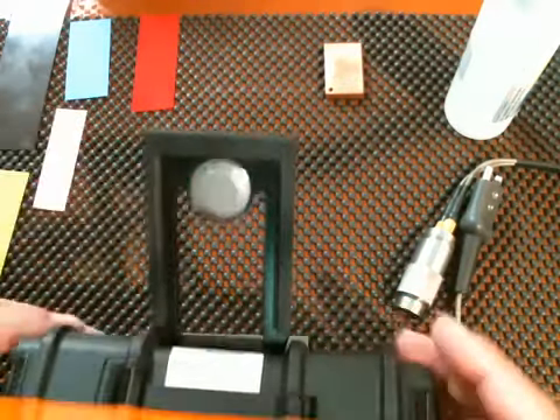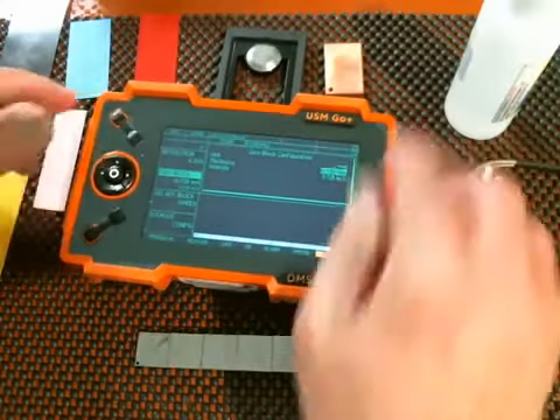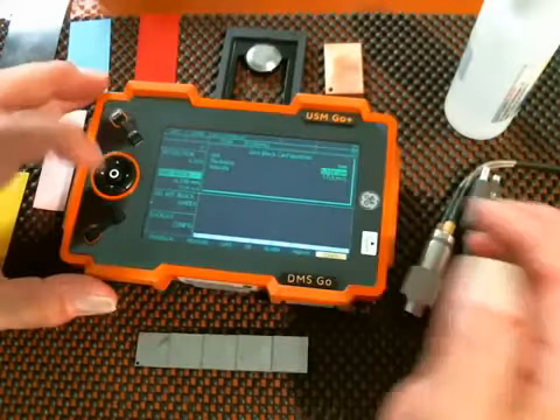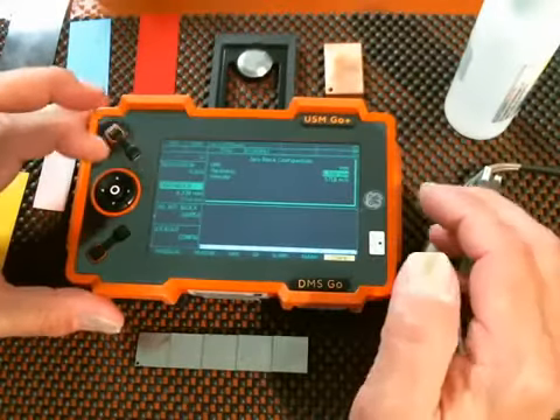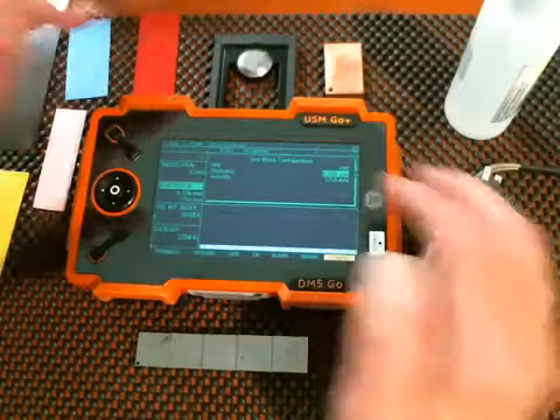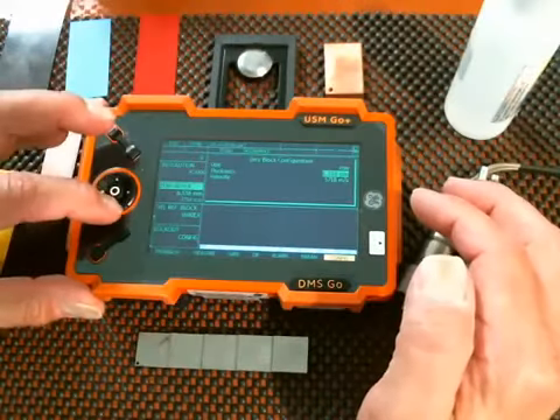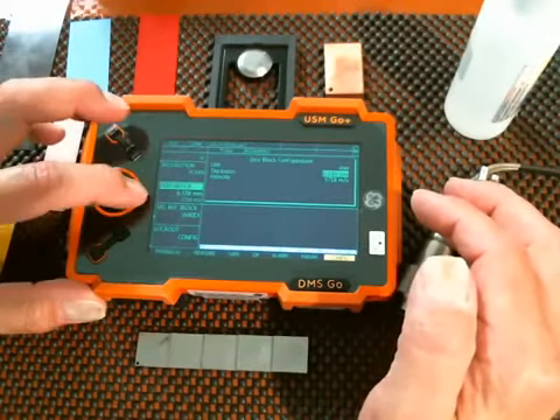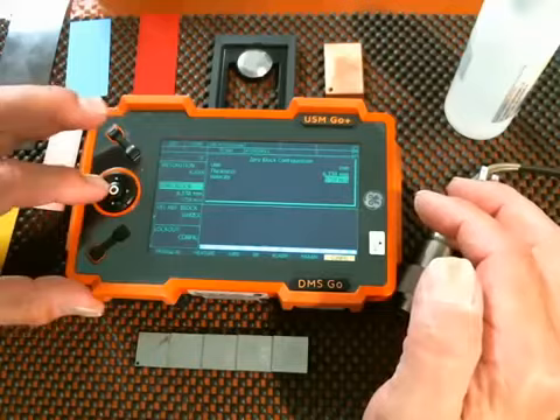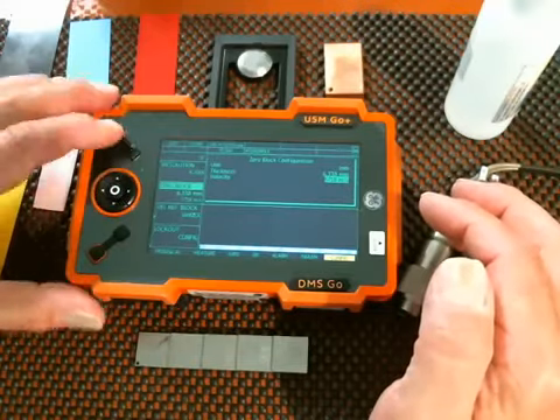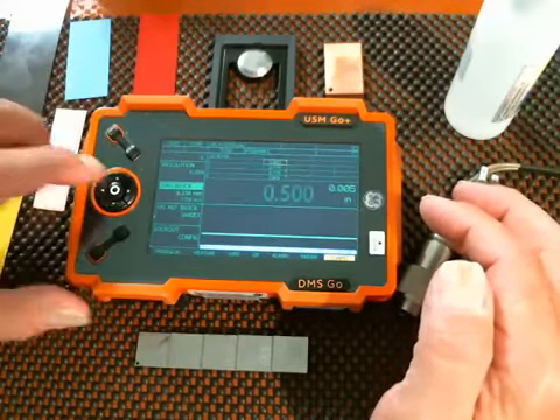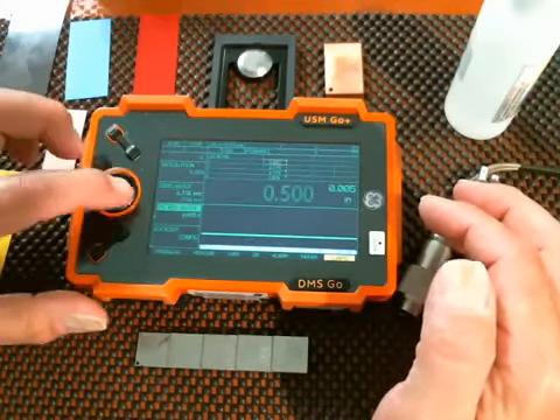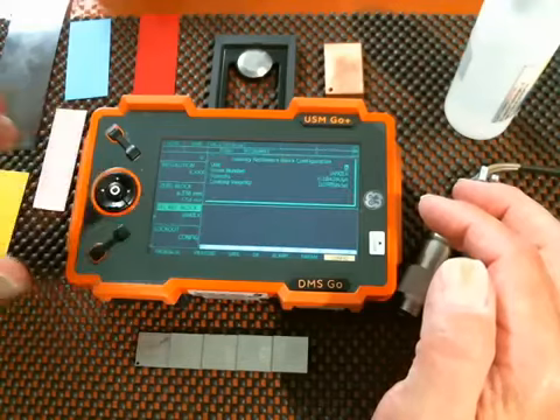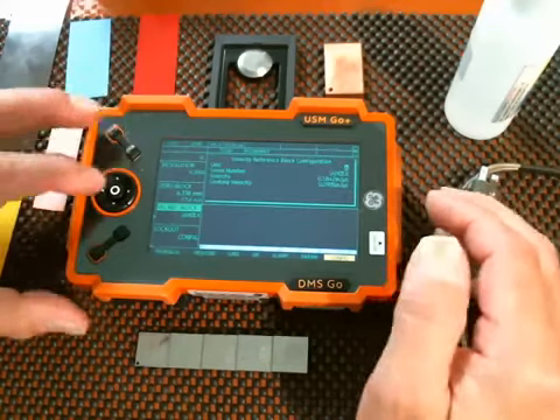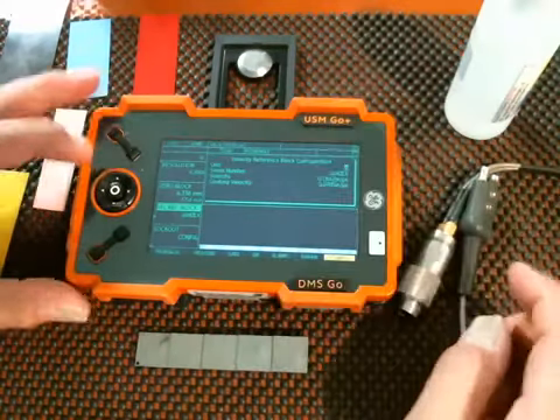We always mark the blocks only in metric. You'll notice that the parameters in here for setup are fixed in metric. In this case, 6.338 matches. If I wanted to make a change, up and down to select the item, right and left to adjust the values. Those are correct, so I hit done. Come down to the velocity reference block. Again, I use the right arrow. In here, I can choose whether I want to work in inch or metric.